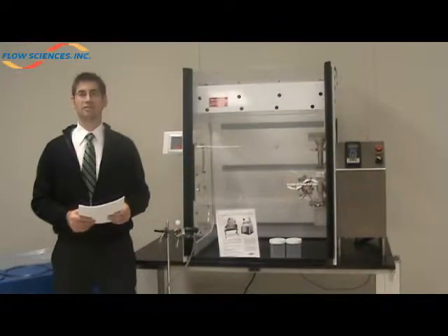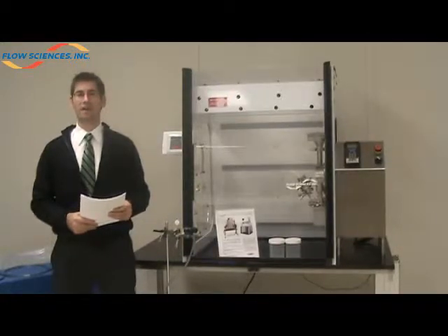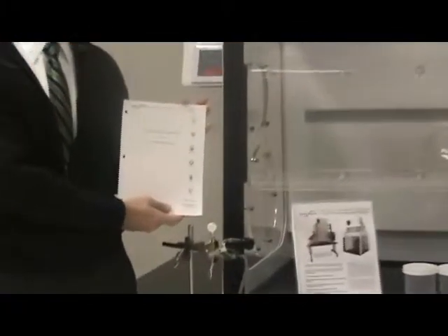This custom-engineered low-flow benchtop powder hood has achieved containment levels of less than 1 microgram per meter cubed. This was measured through factory acceptance testing in our laboratory under ISPE guidelines using lactose as a surrogate powder. A full copy of these test results are available upon request.